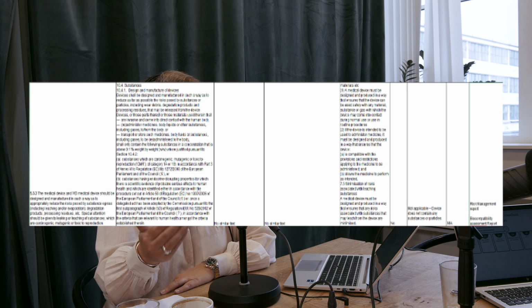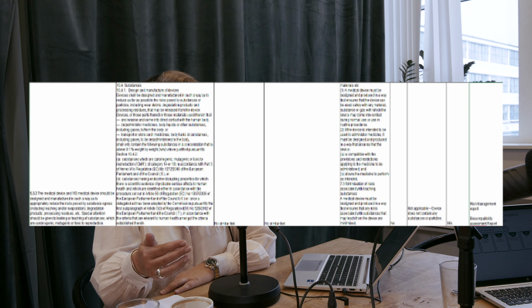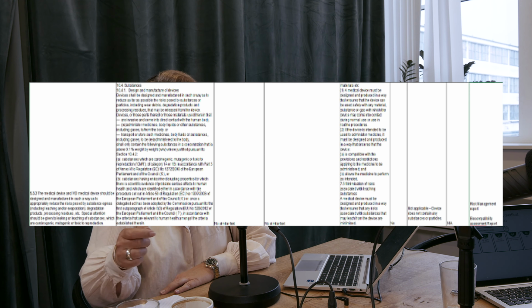And this is also something I would start early. It's basically your plan, right? You start to plan out what you actually need to test to demonstrate each requirement. And the requirements come directly from the regulation. Yeah. And then you have all the other guidelines to support that. And here it's the same, right? You have to put in your justification if you write that, oh, I don't think this requirement is applicable. You need to write why. Yeah, exactly, like the classification statement. So you need to evaluate each of them.